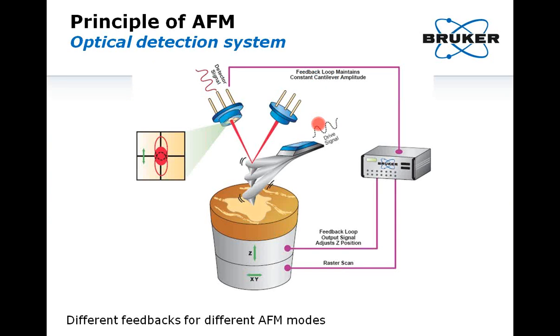Here is a schematic explaining the principle of AFM. The main element of an atomic force microscope is a sharp probe mounted on a cantilever, which is about 100 micrometers in length, and is scanned over the sample surface following its profile. Each local change in topography will cause the cantilever to be deflected. A laser beam is sent onto the reflective back side of the cantilever, and the laser spot will move according to the bending of the cantilever. The primary goal of an AFM is to generate a height profile of the surface, but much more additional information can be acquired simultaneously. Depending on the different existing modes, the feedback can be based on deflection (contact mode), amplitude (tapping mode), or other signals.